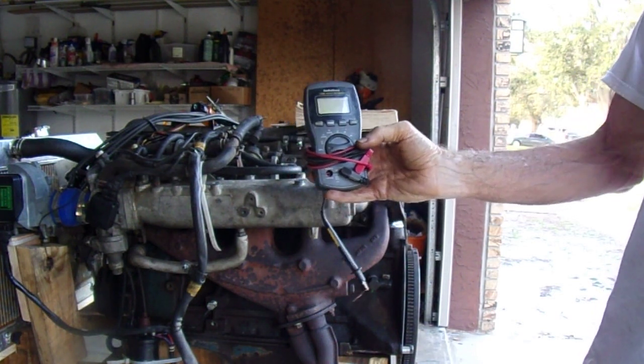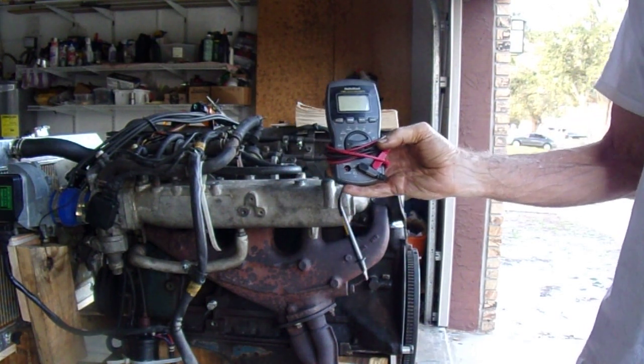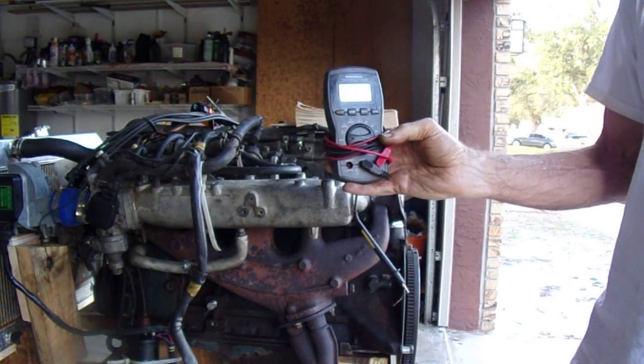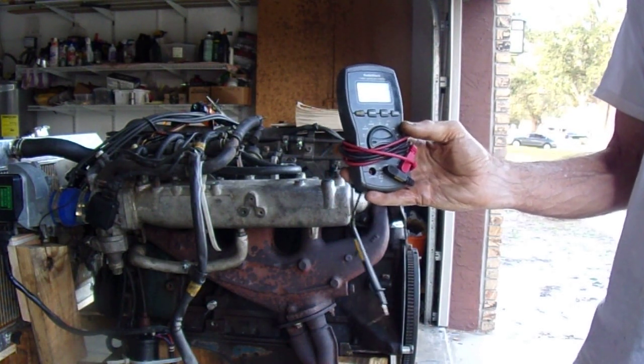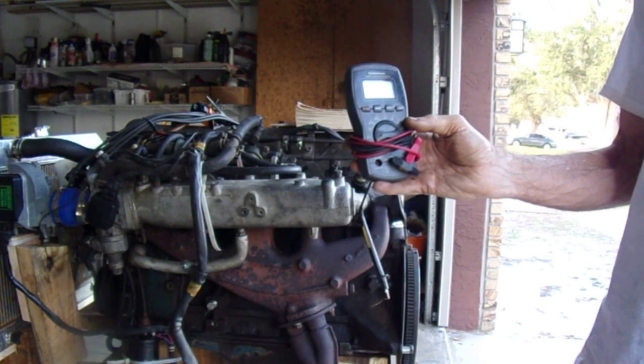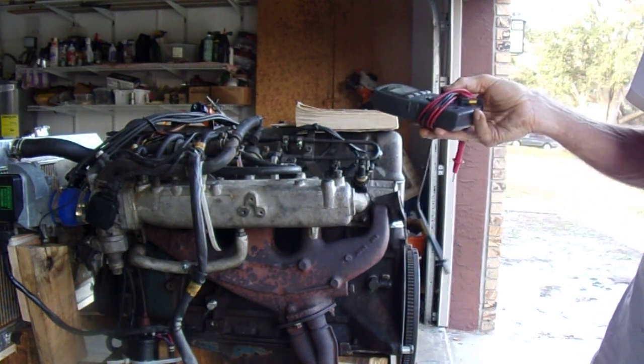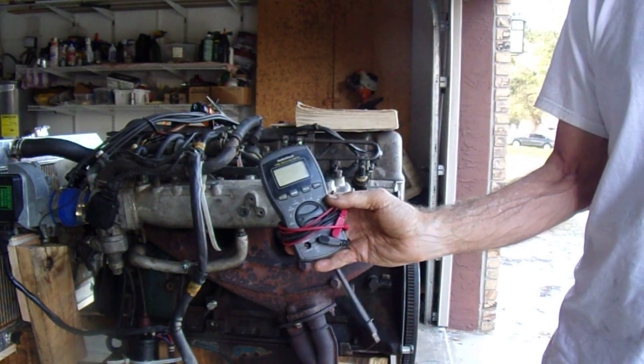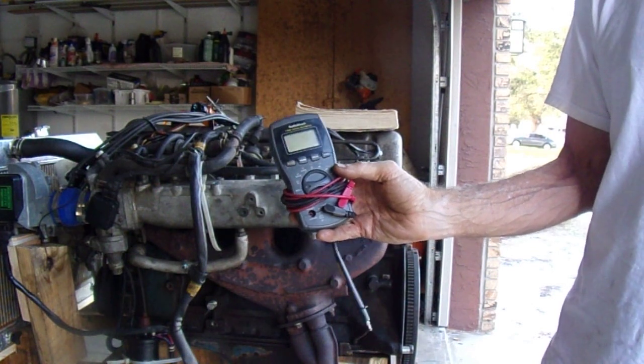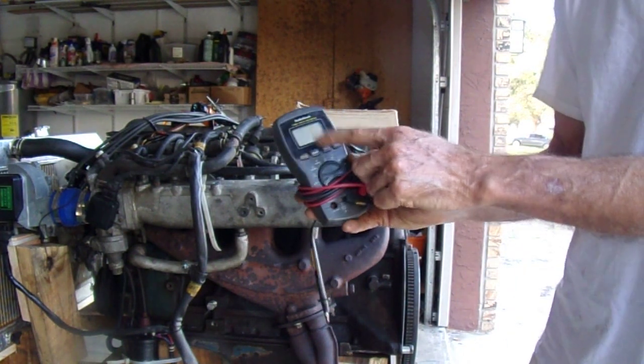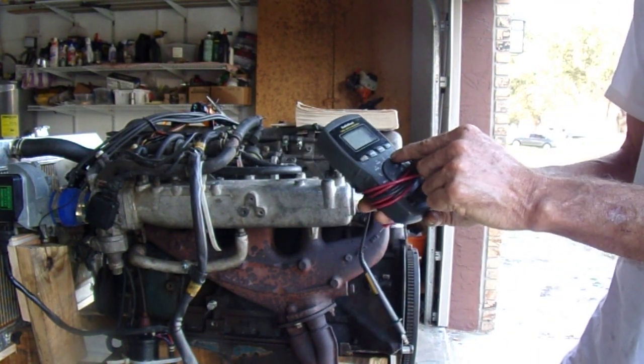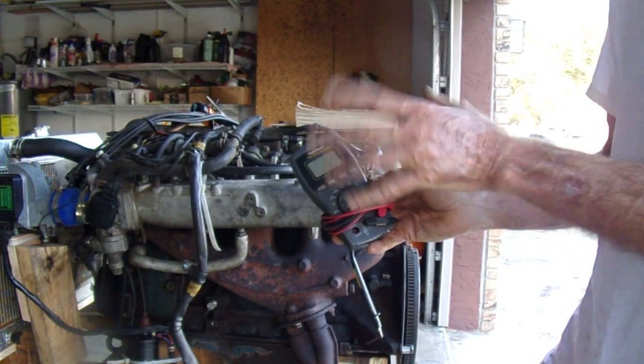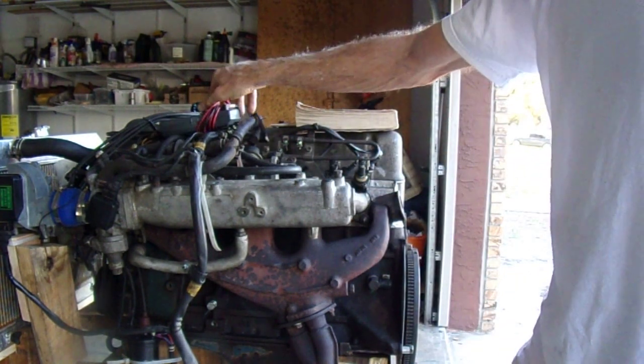I use that primarily for checking resistance. I don't like using this to check voltage. It's okay if you just want a gross number, but if you want to test the circuit, you're better off using those test lights because it puts a load on the circuit. If you have a high resistance something or other, it's not good. Also, what I like about this is I put it on the tone for continuity. That makes it easy to check continuity, and I'll talk about that in a minute.